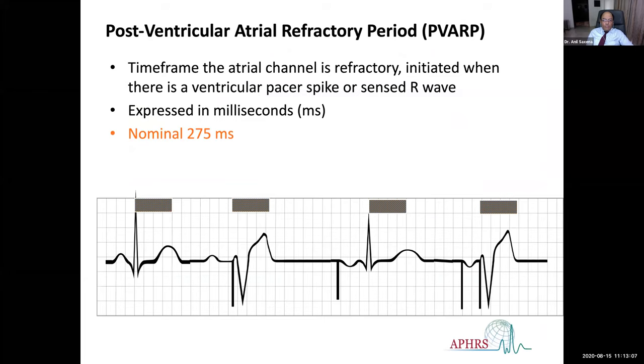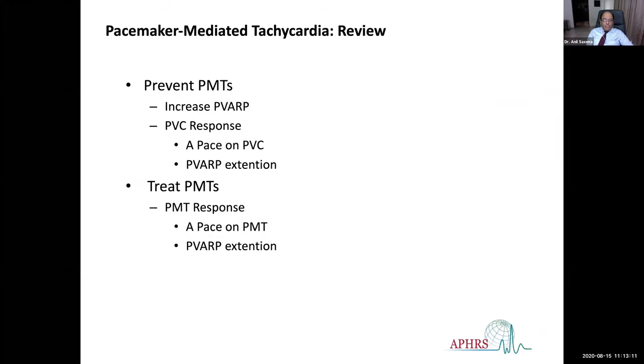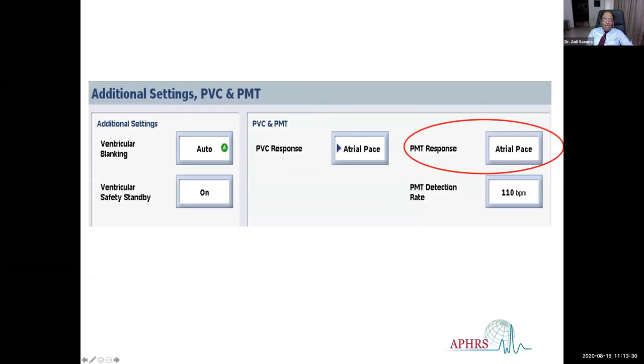Pacemakers now have an algorithm which gives an extension of PVARP in response to a PVC, called PVARP extension. Every time the pacemaker senses a PVC, it can do one of two things: it can give a PVARP extension, or it can pace on PVC. To treat PMT, pacemaker-mediated tachycardia, it can either pace on PMT or give a PVARP extension.